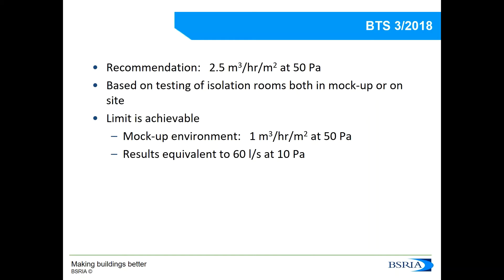2.5 is not a random number — it is based on BSRIA's experience with airtightness. We have a very large airtightness department. We agreed on 2.5, but in reality, if you can achieve a smaller number it would be even better. This number is achievable: for example, in a mock-up environment at BSRIA, when we took care of airtightness from the design stage, we achieved 1 cubic metre per hour per square metre. There are hospitals and other isolation rooms that can actually achieve this limit or lower.